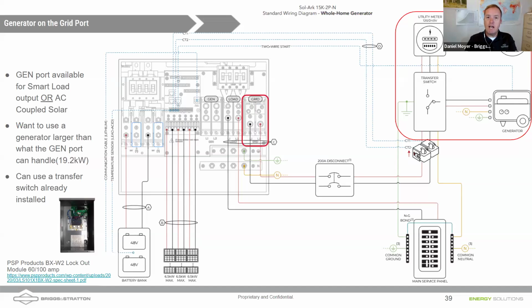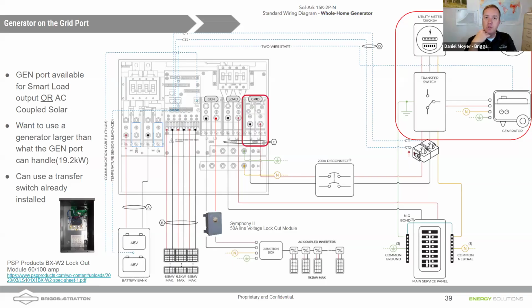Easy. What can happen though is when we try to AC couple solar, so we bring in our AC coupled solar, and earlier I had mentioned we use frequency shifting to curtail the charge of microinverters or string inverters. All these hybrid inverters are grid following when they're running off of the grid, and they're grid forming when they're running off the batteries. When they're able to form a grid while running off the batteries, that's when we have the ability to do frequency shifting, and we can shut off the AC coupled solar to prevent the batteries from being overcharged.